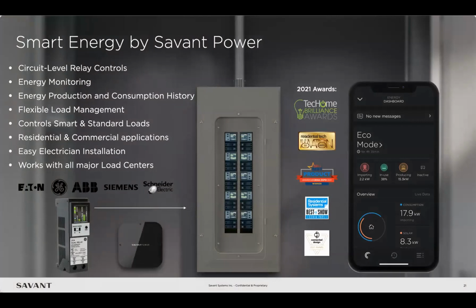On each of the modules that we have, they have a variety of functions. The most critical one is the circuit level relay control. As mentioned, there is no overcurrent protection, so we're simply passing the power through to the end product. We have a relay built into the module to turn it on and off according to a certain set of scenes.